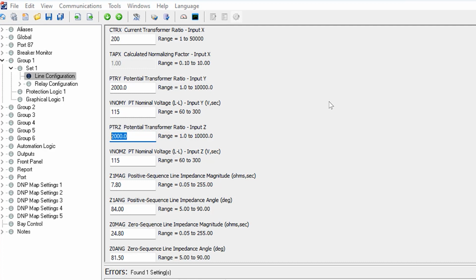Now, if we have a 230 kV transmission line, if we divide 230,000 by 2000, we get that the secondary voltage is 115 volts line to line. So that's going to be the nominal voltage for both the Y terminal and the Z terminal. Again, that's the line-to-line voltage, not the line-to-neutral voltage. That's going to be important when we get to the sync check settings.